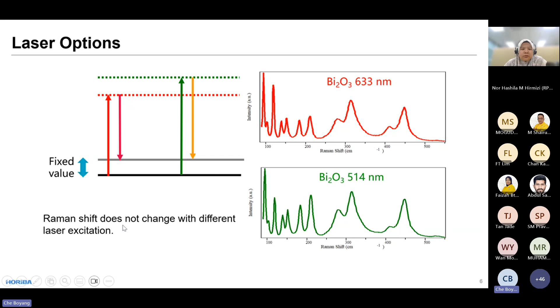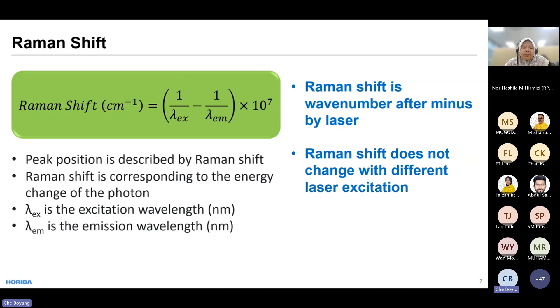So why is it like this? It's because we are not really using the wavelength, but the Raman shift as the X value of your Raman spectrum. This is how the Raman shift is calculated. In the equation, we use the excitation wavelength minus your emitted signal. So it's not an absolute value, it's a relative value with regard to your laser. By doing this calculation, we make sure the Raman shift is always the same, even if you are using different laser wavelengths.